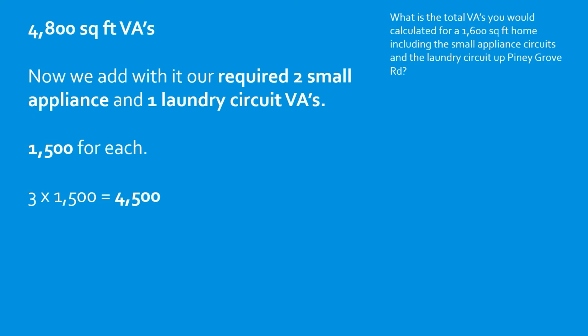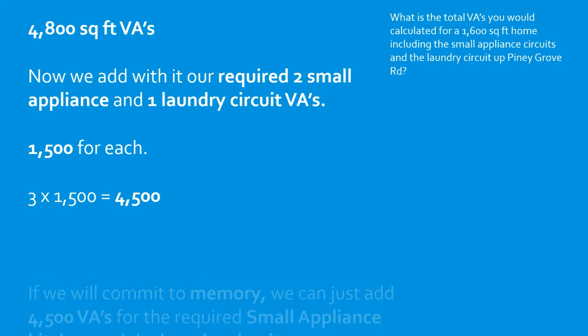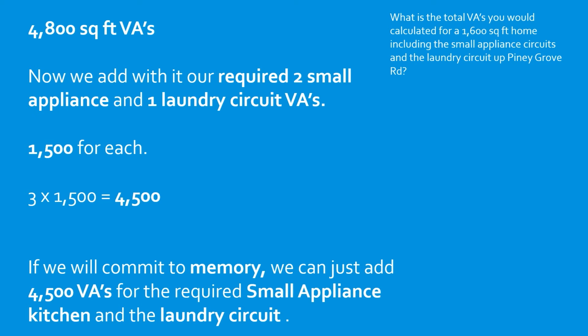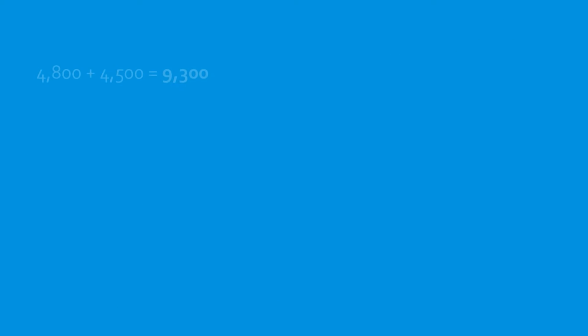I do want to note that anytime you're doing a load calculation, do your square foot VAs and then just add 4,500 to it. In your questions, it's almost never going to mention the small appliance and the laundry circuit. They just assume that you know that, so you have to remember to add those 4,500 VAs. If we commit that to memory, we just add the 4,500 for the small appliance and the laundry circuit to each question. So we add those two together, and that gives us 9,300 VAs.